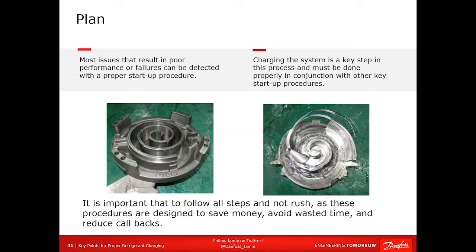The liquid doesn't directly destroy the scroll — what happens is the liquid dry-cleans the bearing and the bearing seizes. The mobile scroll has a large counterweight on it that doesn't stop all at once, so when that bearing seized, the counterweight and mobile scroll kept going and wrapped itself up in the fixed scroll, breaking it apart — it literally looked like it exploded. Proper charging matters: one-third of compressors sitting in a warranty pile looked like this. It costs contractors, wholesalers, and everybody a lot of money — and it is completely under the control of the person doing the charging.